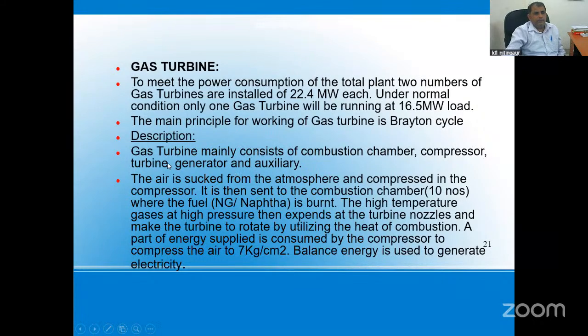And here the air is sucked from the atmosphere and compressed in the compressor. The compressor has 17 stages and develops a pressure of only 7.4 to 8 kg per cm square, but the flow is huge. Its capacity is 240,000 CFM. The air is then sent to the combustion chamber, where the fuel mixes with the air and combustion takes place.